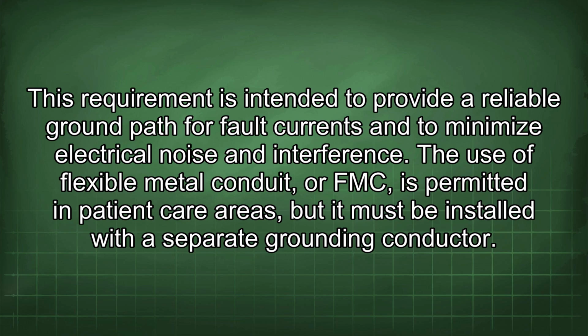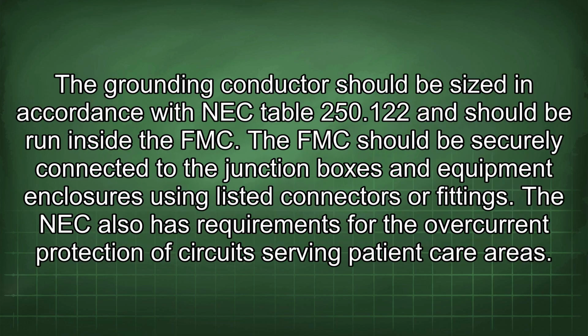The use of flexible metal conduit, or FMC, is permitted in patient care areas, but it must be installed with a separate grounding conductor. The grounding conductor should be sized in accordance with NEC Table 250.122 and should be run inside the FMC. The FMC should be securely connected to the junction boxes and equipment enclosures using listed connectors or fittings.